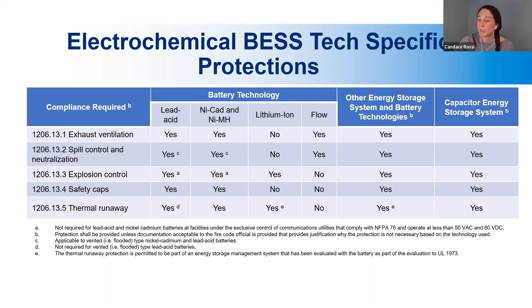So here is the exhaust ventilation, which I stated is required for lead acid batteries. The ventilation is designed to limit the maximum concentration of flammable gas to 25% of the lower flammability limit, or provide continuous ventilation. There needs to be standby power for a minimum of 2 hours, and exhaust ventilation shall be supervised by a central or remote station. As part of the exhaust ventilation requirement, a gas detection system is required to monitor the levels of gas in the unit. This will trigger appropriate ventilation and inform operators of unusual levels of off-gassing. Any failure of the gas detection system will also trigger a trouble signal to the battery management system.